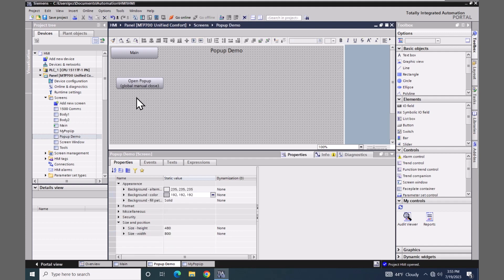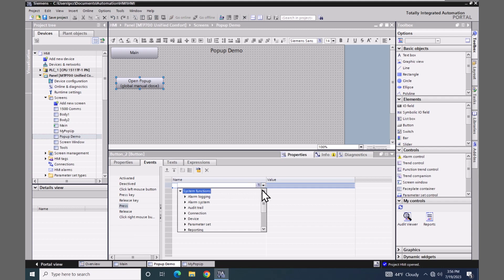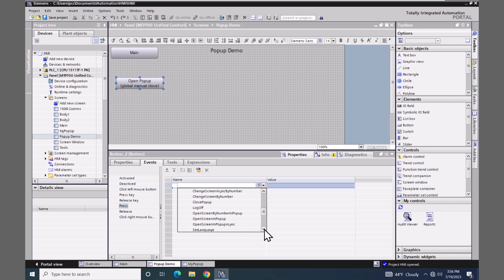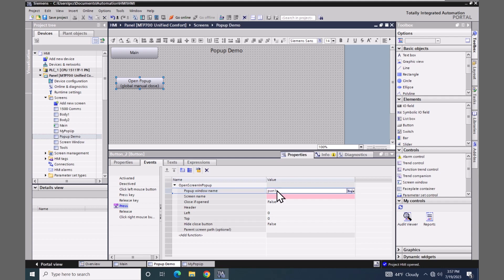The first approach we are going to use to open the pop-up window is going to be global in nature. When the pop-up is global, switching screens will not close the pop-up window automatically. I'll select the push button, go down to the events area, select the press event, and go into the screen category of functions. There are a couple of different functions for opening a pop-up — we are going to use the Open Screen in Pop-up function. The first parameter is a unique window name, which is an identifier for the window being opened. I'm going to use pwn1 for pop-up window name one.